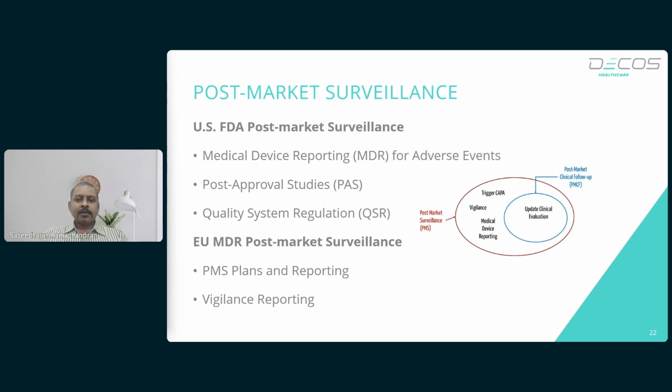Under the EU MDR, post-market surveillance is a critical component of the regulatory framework designed to ensure the safety and performance of medical devices after they receive CE marking. Manufacturers are required to establish and implement a comprehensive post-market surveillance system that includes PMS plans and reporting, where the manufacturers are required to create detailed PMS plans specifying how they will monitor the device after market release. Regular periodic safety update reports (PSUR) must be submitted summarizing device performance and safety data. This helps authorities monitor for any emerging risks.